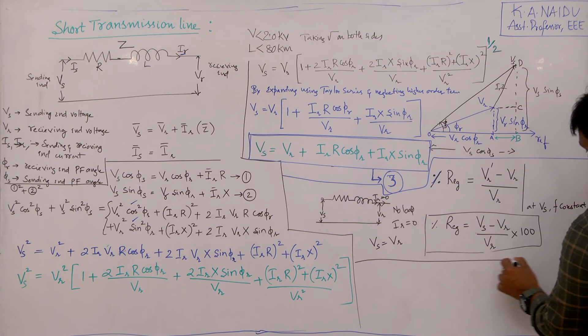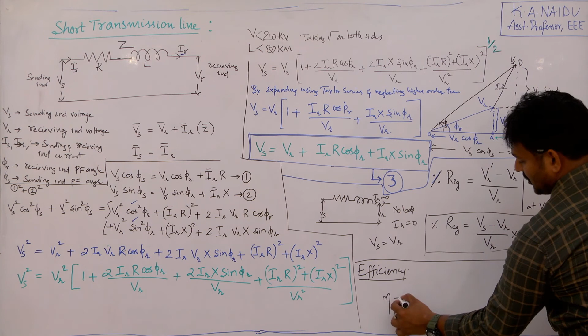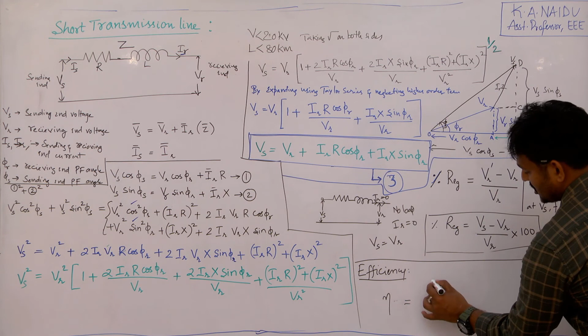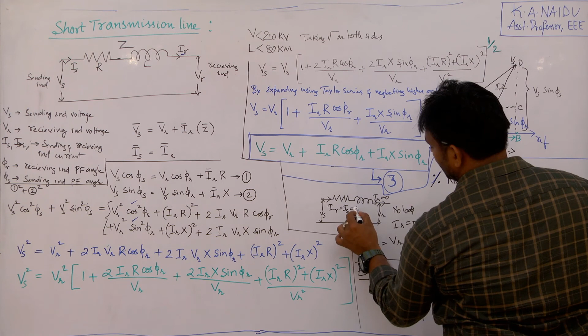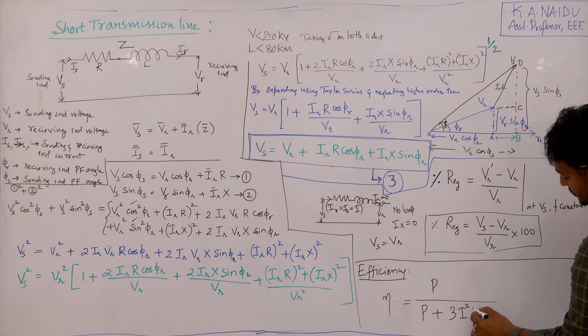Okay. Next, efficiency. What is efficiency? Power delivered at the receiving end upon power that is at the sending end, or you can also write it as the power that is delivered to the receiving end upon power delivered to the receiving end plus whatever the I square R losses. Generally the transmission lines are 3-phase transmission lines. Therefore efficiency can be written as, suppose P is the power that is delivered at the receiving end, and then P by, there are 3 lines, and the total current flowing is IR. The total current that is flowing through this R is IR, which is same as IS, that is equal to, let us say, I at full load. This is at full load. So I square R. If you want percentage, simply multiply with 100.